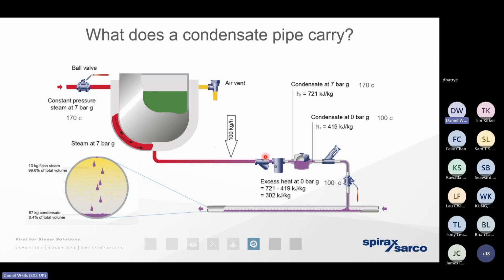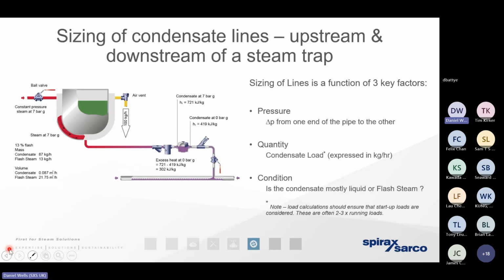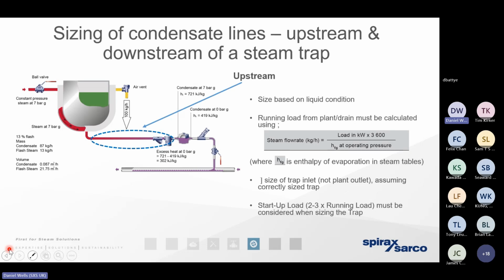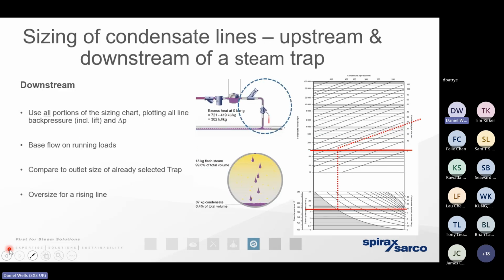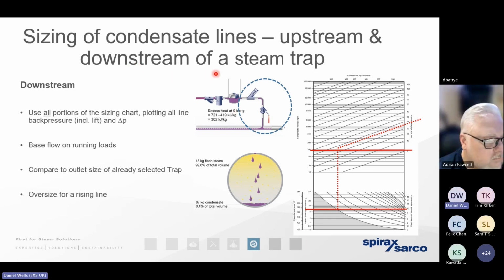The problem is, as that condensate depressurizes when it moves across the trap, that's when that high energy content needs to be given up. A certain mass or percentage of the condensate is going to boil off, change state back to steam as a gas, and that factor of expansion downstream of the trap is going to be significant. So of course, we need to vent that away. If we're not venting that expansion away, then we're going to get significant damage imparted to the infrastructure itself. That expansion means that we could have a lot of knocking, banging, or damage in the infrastructure. But it also means that that expansion can place an unnecessary back pressure on that trap that is a further barrier in allowing the condensate to drain away at the appropriate rate.